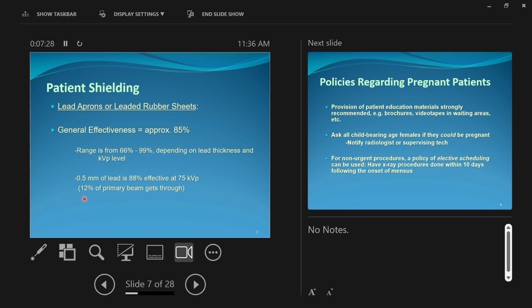So no shields block everything, right? Even the thickest shields we have can block up to 99%, but will not block 100%. That's just not possible. Your lead aprons that are not designed to be used in the path of the primary beam, the lap aprons, those kind, are only required to be 0.25 millimeters thick. So 0.25, a quarter millimeter. Most of them are a half of a millimeter just because. Okay, so twice as thick just because.